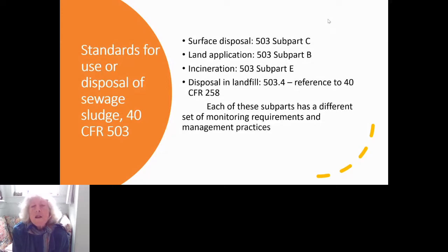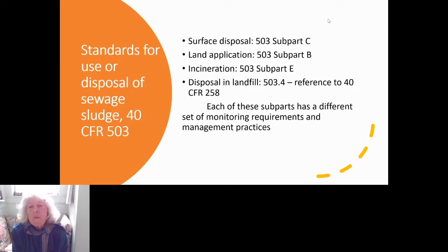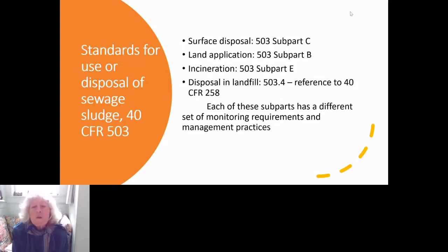In our standards for the use or disposal of sewage sludge, surface disposal is covered at 40 CFR 503 Subpart C. Land application for growing crops is in 503 Subpart B, and incineration is in 503 Subpart E. In EPA Region 9, we only have one incinerator — this is much more common on the East Coast and north central U.S. Disposal in a landfill references 40 CFR 258. Each disposal method has a different set of monitoring requirements and management practices.